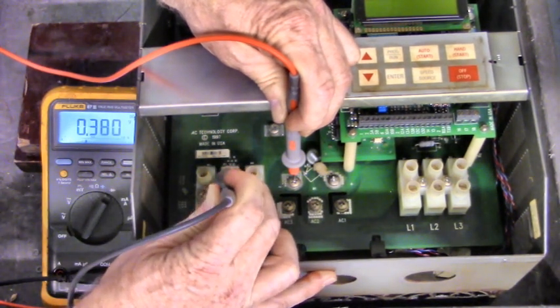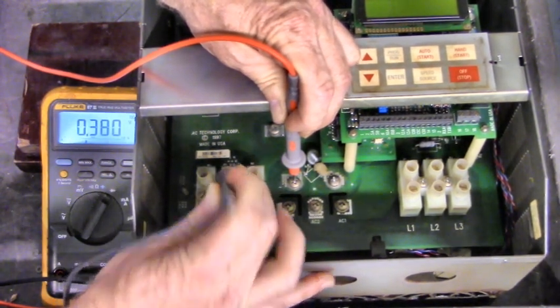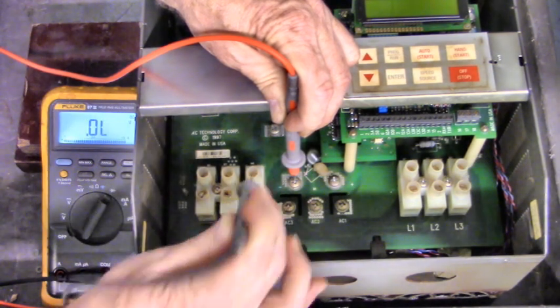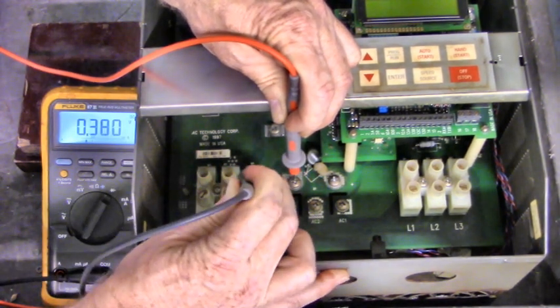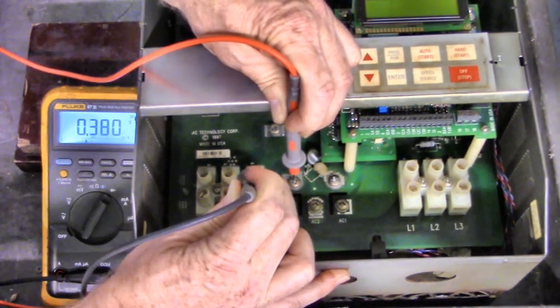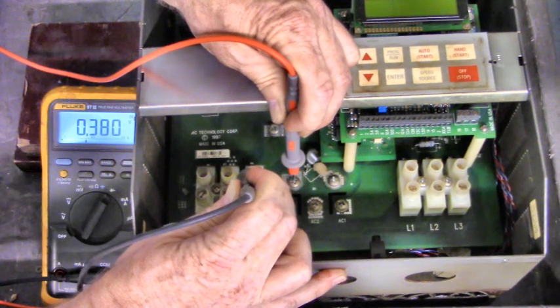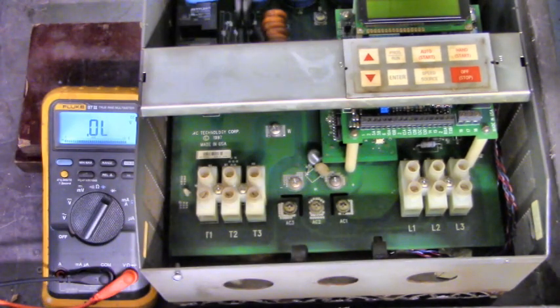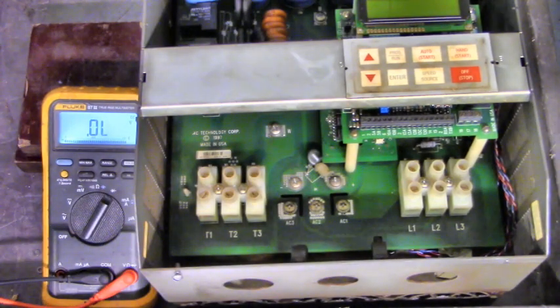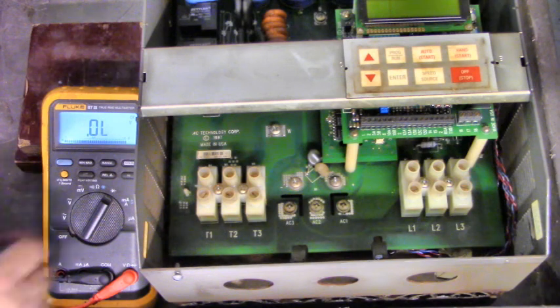T2, .380 volt diode drop. That's good. T3, .380 volt diode drop. The three-phase bridge and the IGBT is good.